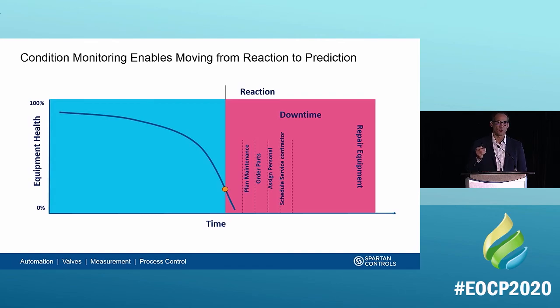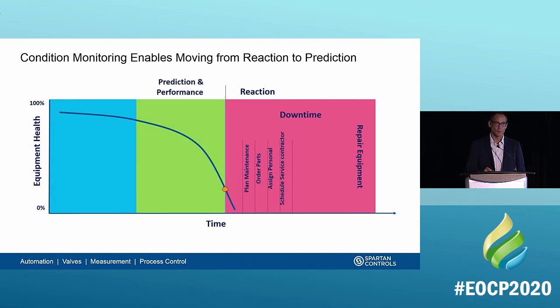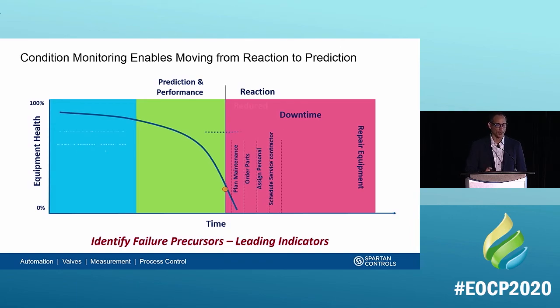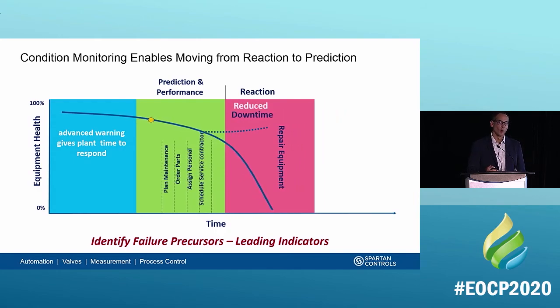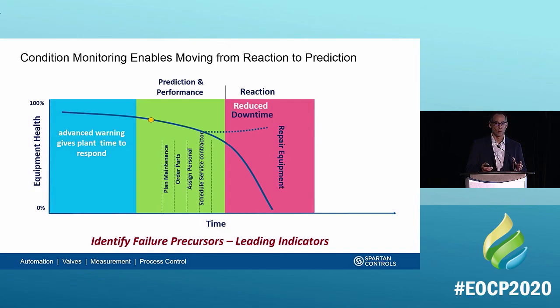With condition monitoring, if we can determine that fault prior to it causing a shutdown, we have an opportunity to improve both the amount of time the device is down and the cost associated with that. If we can detect that fault much earlier — in the predictive green section — we can do all the scheduling and planning work while the equipment is still running. That minimizes the downtime needed to affect the repair. No matter what happens, we have to repair the fault, but if we do all the planning while the machinery is running, our actual downtime is significantly less.